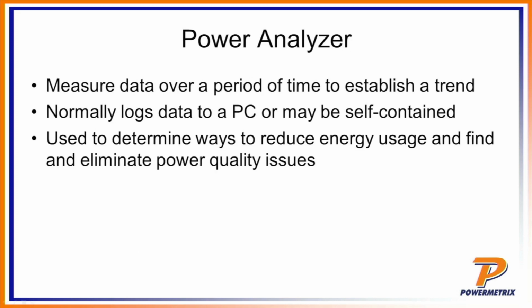The power analyzer is designed such that it can take data over long periods of time, because a lot of times power quality issues may not be easily detected just by one trip. A lot of power quality issues may be very momentary, very intermittent, meaning that you really have to look at a long set of data over the course of hours or days to be able to catch it. Sometimes you're looking for a trend in terms of voltages going up and down, and so you're trying to correlate those trends with equipment being turned on and off. And so really the power analyzer has to have the ability to monitor all those things we just talked about over a long period of time.